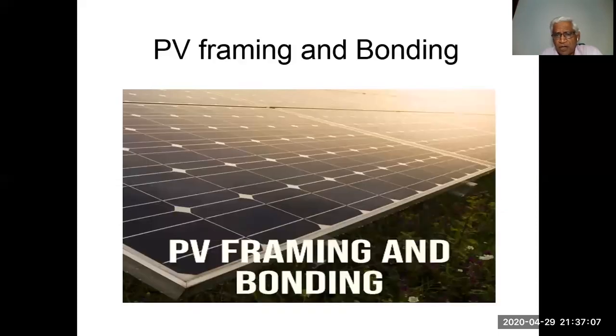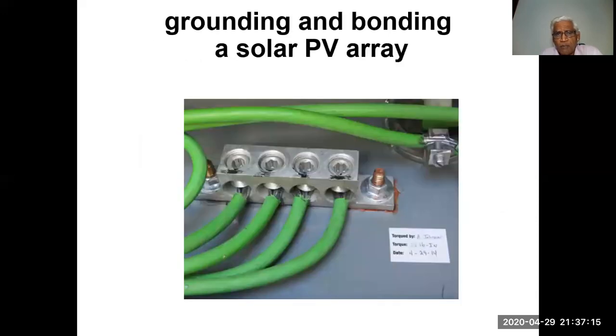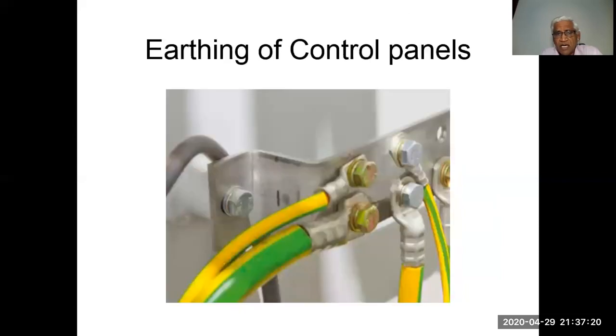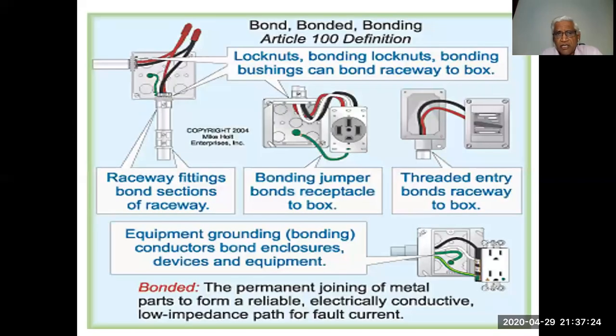PV framing and bonding. The entire frame we see is a large array, so all the frames have been earthed. Grounding and bonding of solar PV arrays. And this is earthing of a control panel. And this is bonded; bonding is in Article 100 of the definitions of NEC. You can notice that the green wire is being earthed to the metallic container.